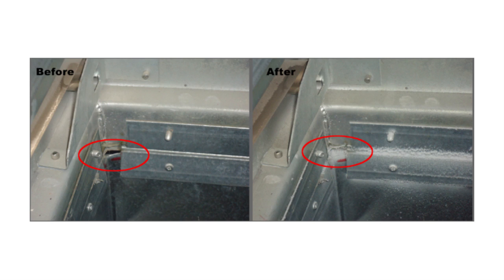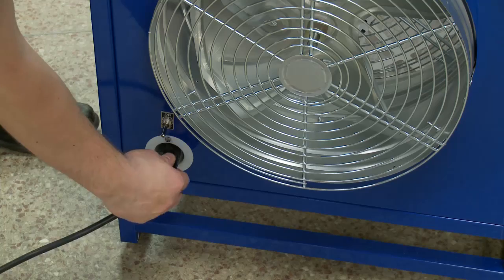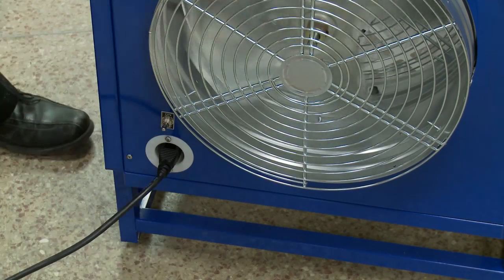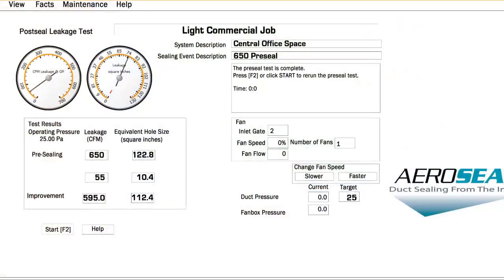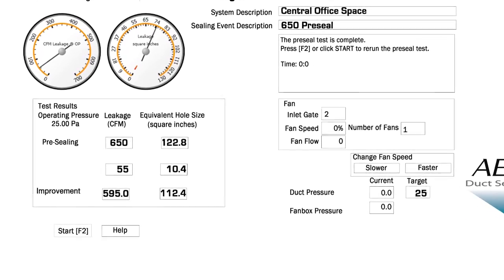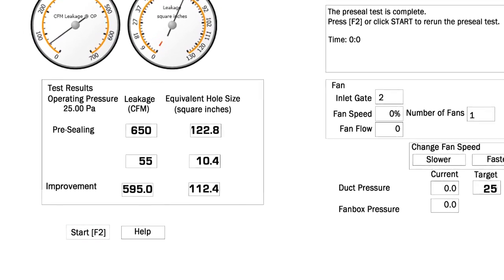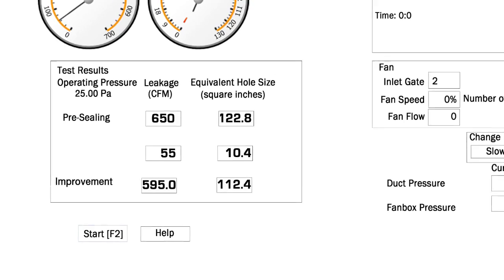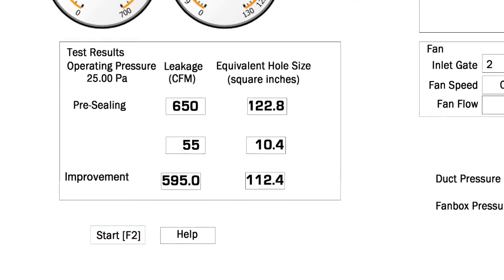The Aeroseal process can seal holes as big as 5/8 of an inch without coating the ductwork. You will want to run scrubber fans to clean the air in case of any overspray. We took the initial leakage rate prior to sealing, and now we must take the final leakage rate after the process of sealing. This report tells us how well the process worked.